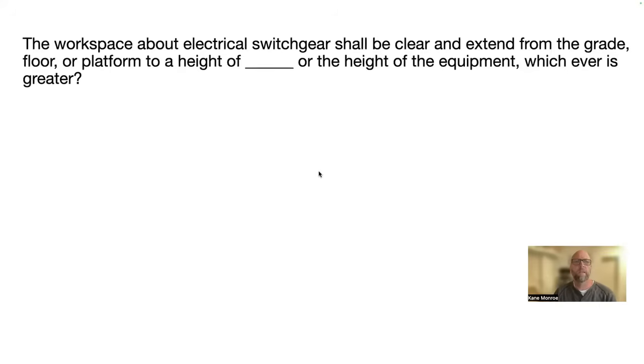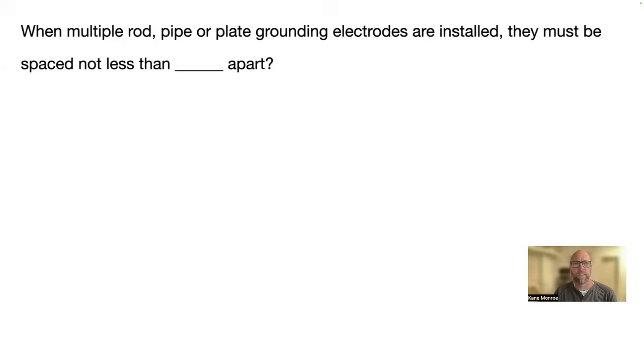All right, the workspace about electrical switchgear shall be clear and extended from the grade floor or platform to the height of blank or the height of the equipment, whichever is greater. So they're asking for the height of the workspace and that's six and a half feet. NEC 110.26 A3. So make sure you guys are highlighting those. 110.26 A3. If I'm going too fast, stop the video and make sure you get this information down.